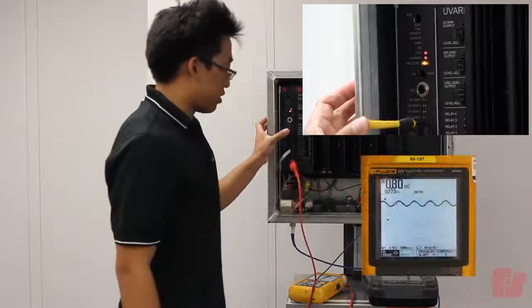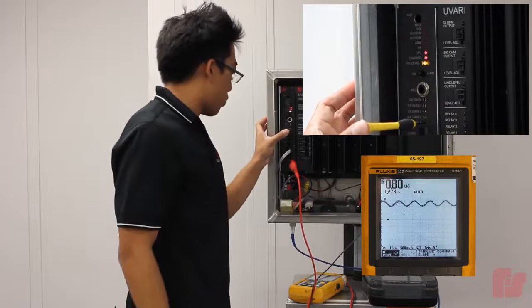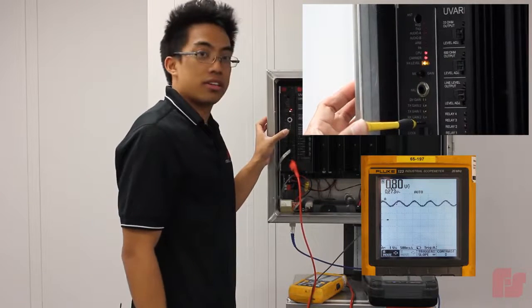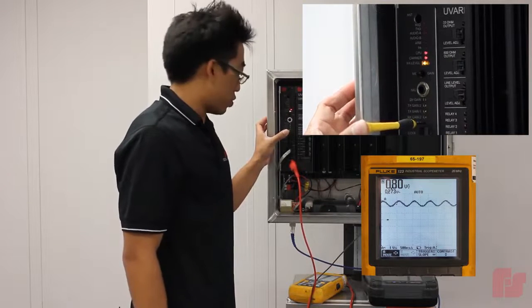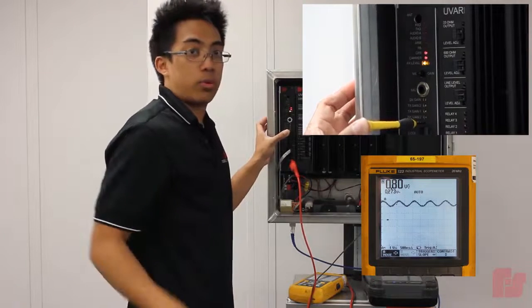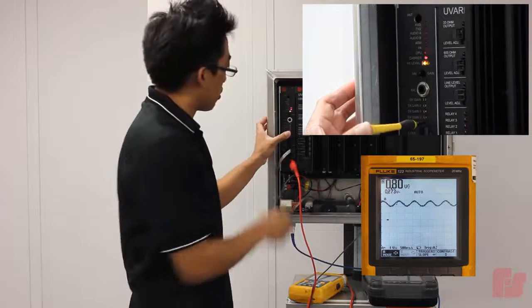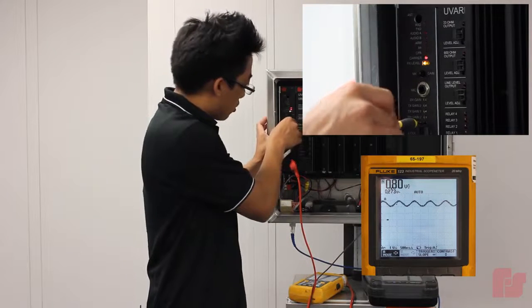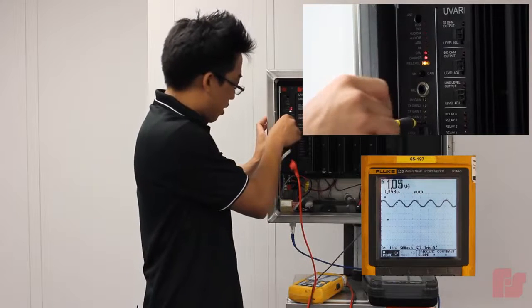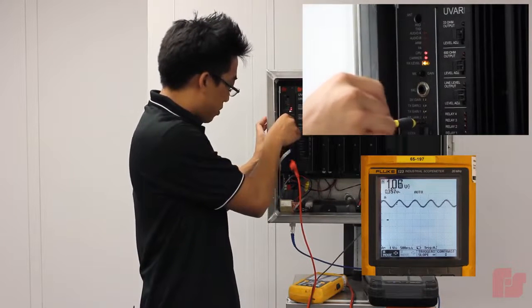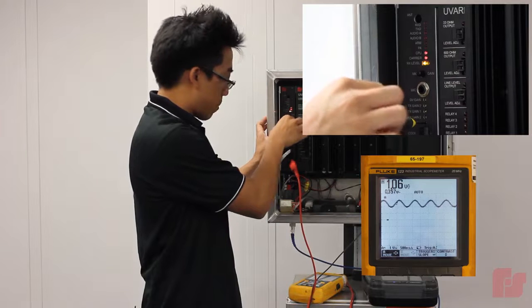So right now my level is a little low. It's at 0.8 volts peak to peak and we want that at 1 volt peak to peak. So I'm just going to turn this RX gain pot just a little bit to get the proper signal.